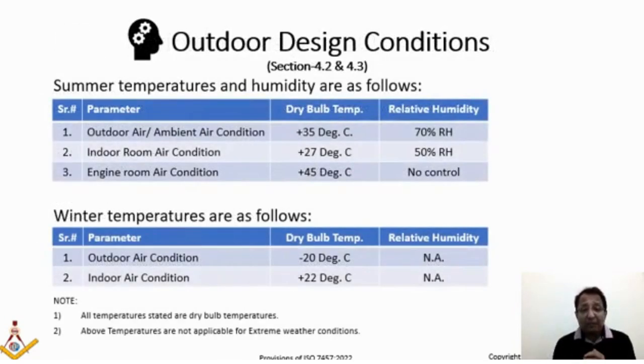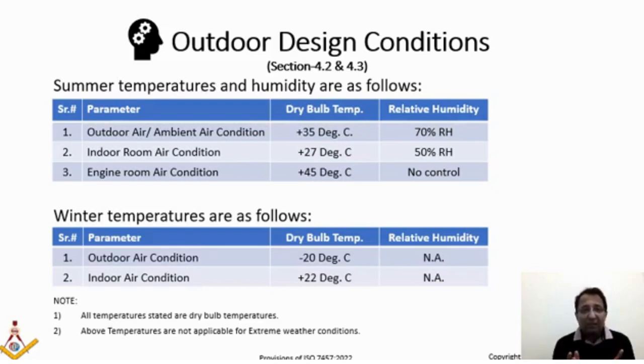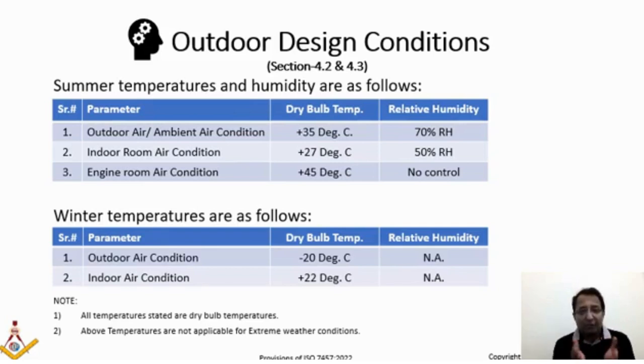This slide talks about outdoor design conditions. Sections 4.2 and 4.3 of this standard define summer temperatures and humidity and winter temperatures for ships. Since a ship moves from one location to another, we cannot take a particular fixed temperature. But if the ship is constantly moving in the North Sea or Middle East only, we take those respective regional temperatures and design based on that.